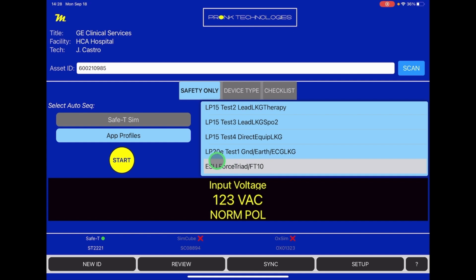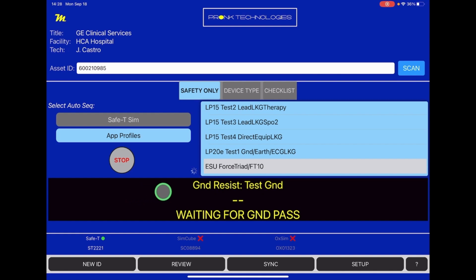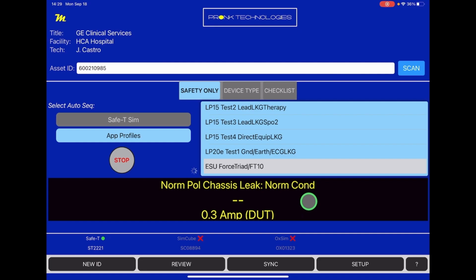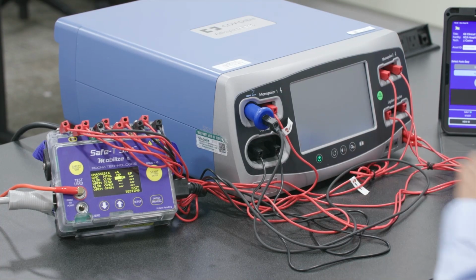Once we've done that, we start the test and the analyzer will wake up and automatically start the first test. In this case, you can see via the Mobilize app, it's running the ground resistance test. In the center here is the measured values, and it's going to perform that test. Once we get to the next test, we want to go ahead and power on the ESU unit so that we could perform the rest of the testing that we need to.